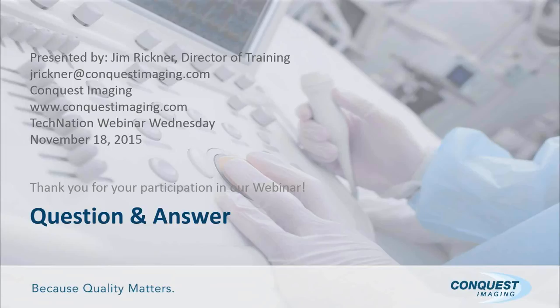The first question: you mentioned the importance of PMs to prevent system failures. What is a recommended interval for PMs? The OEM in this case says that the system should be PM'd every 12 months. I'd just like to add that there are several accreditations, such as the American College of Radiology, that require the PM to be performed twice a year. So it really is OEM 12 months, but you have to look at your accreditation, if any.